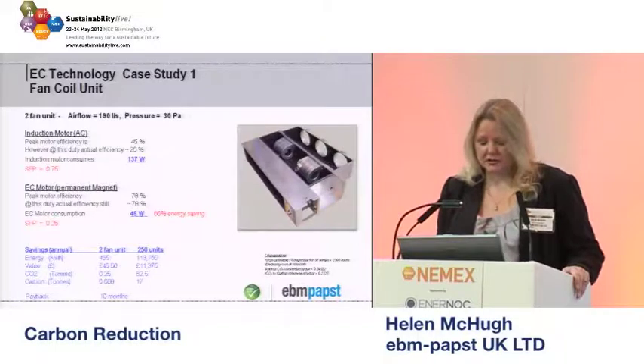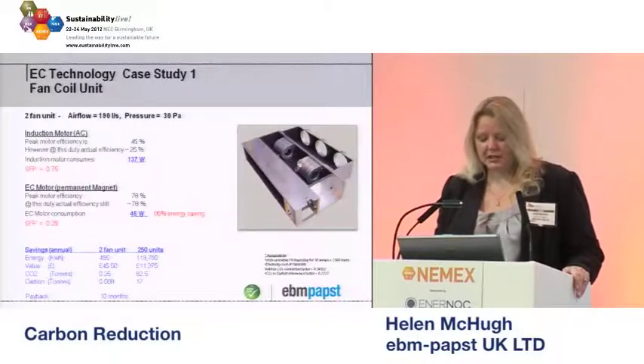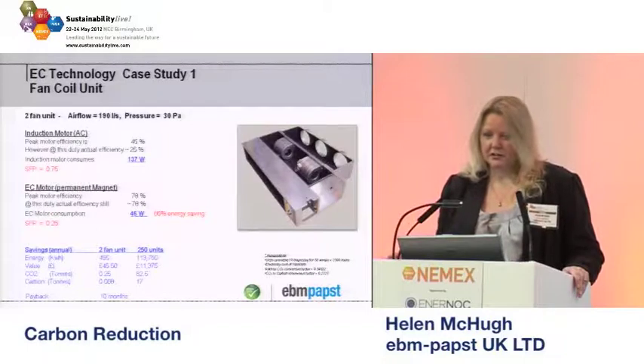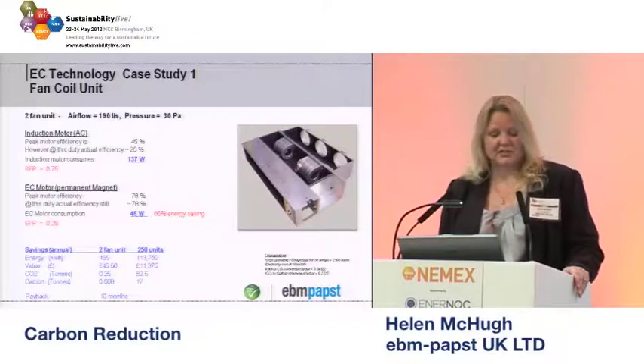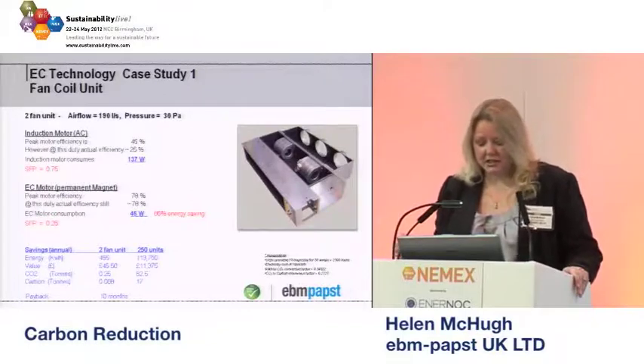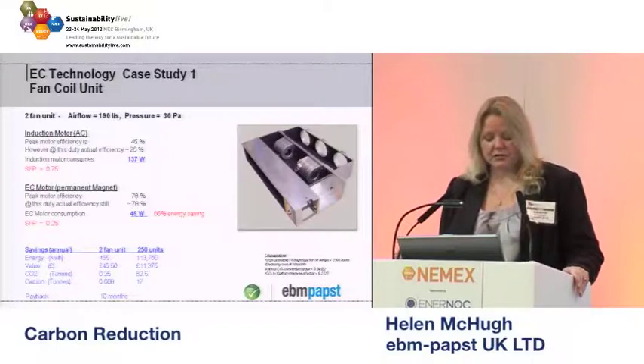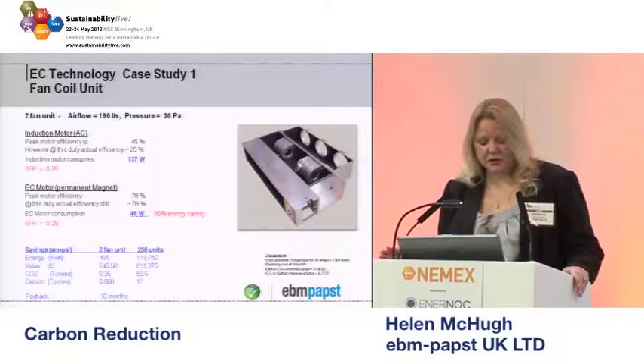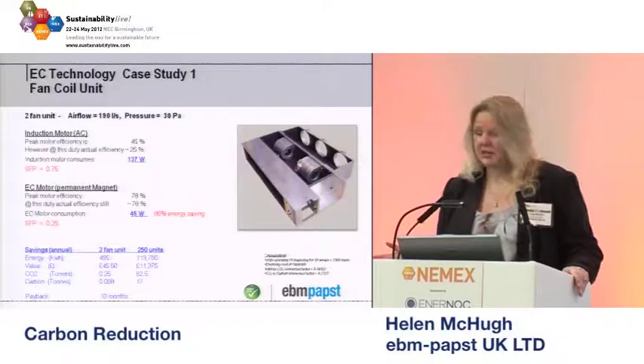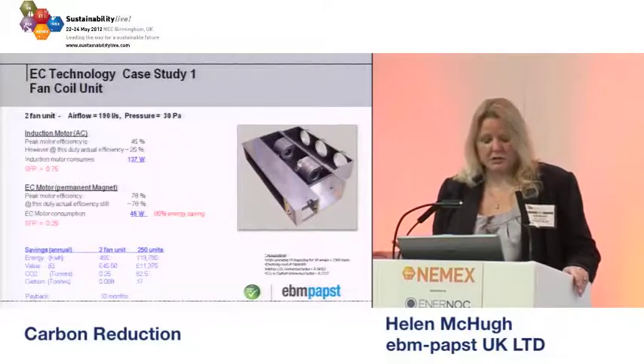So you see there 137 watts. By putting in the EC fans, they're automatically 78% efficient. So you've got a massive saving there. And actually, they don't lose efficiency when they're under higher pressures. So we're looking at 66% energy saving straight away. And in this particular example of 250 units, you see there both the monetary and the carbon savings. And quite importantly is the payback period as well.